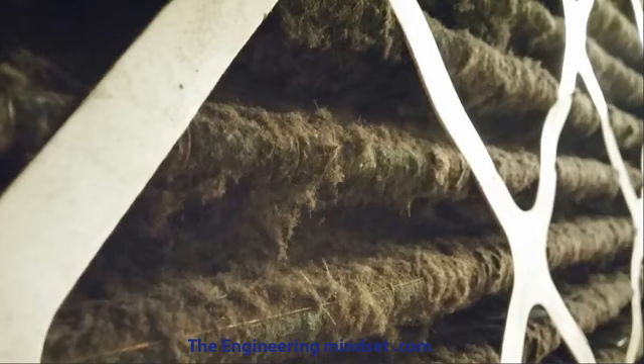And the reason you want to stop all this dust is obviously because it's going to be entering into the building and all the people in there will be breathing this dirty air in. So you want to stop that. But you also want to stop the dust entering further into the AHU, as this will stick to the fans, the motors, the cooling coils. It's going to build up along the inside of the ductwork as well.